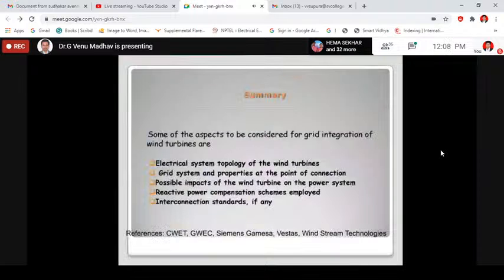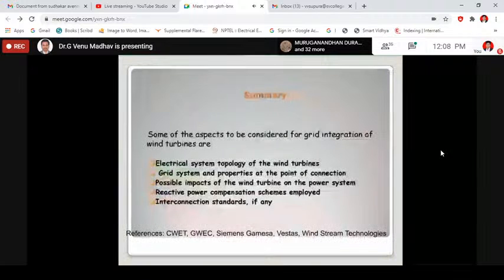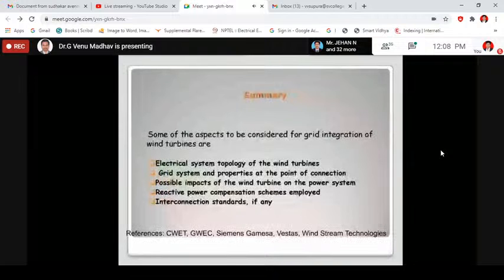So overall summary, conclusions. The electrical system topology of the wind turbines, what we have covered. Okay. Grid system and properties at the point of connection, that is also important, and we need to take care of that. Possible impacts of the wind turbine on the power system. Almost all different types, particularly forecasting within minutes, like 15 minutes nowadays. That is also important. Reactive power compensation schemes employed, say DFIG, if you take, that itself, grid side converter itself will be acting as STATCOM. So that kind of schemes we need to see.